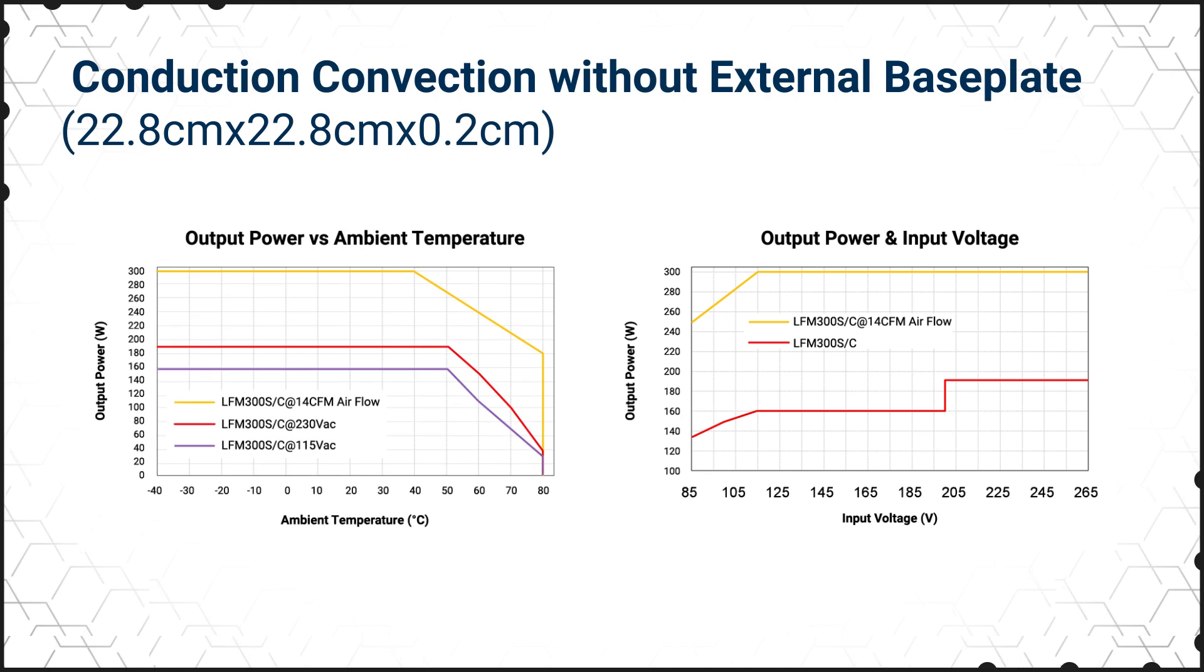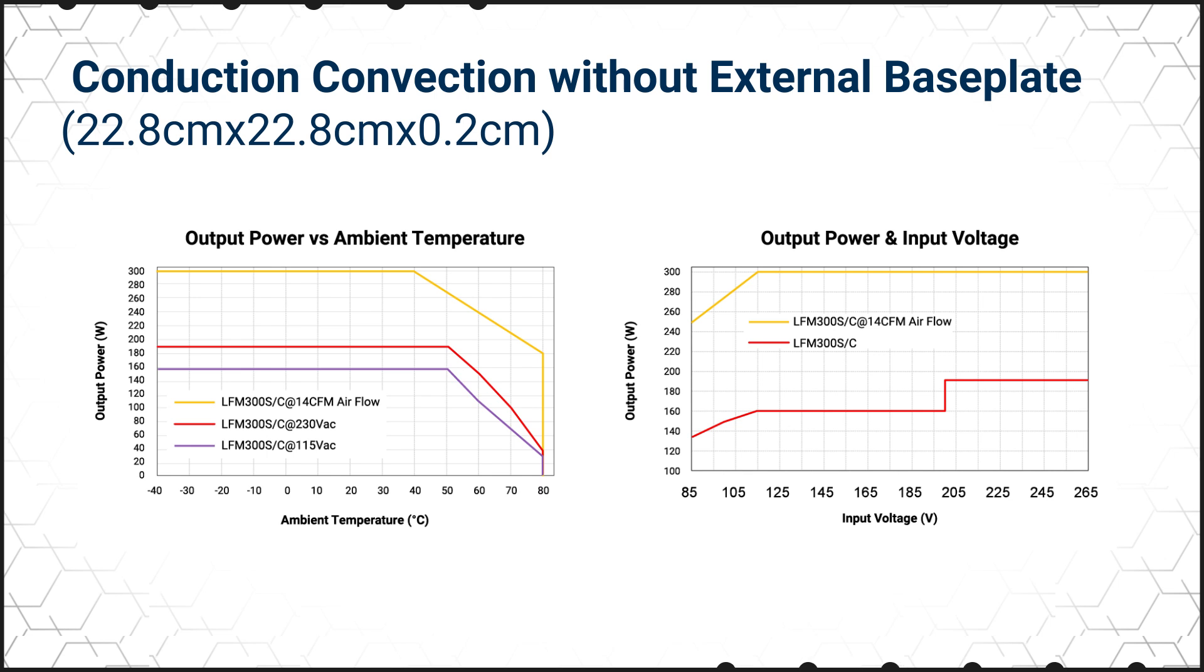To use the full 300 watt output range, an external fan providing 14 CFM of airflow across the power supply is needed, with derating for ambient temperatures up to 80 degrees Celsius.